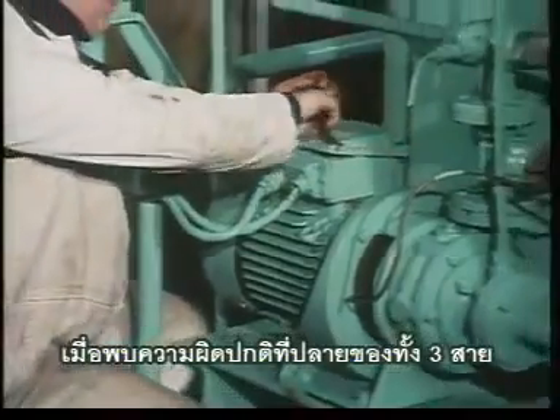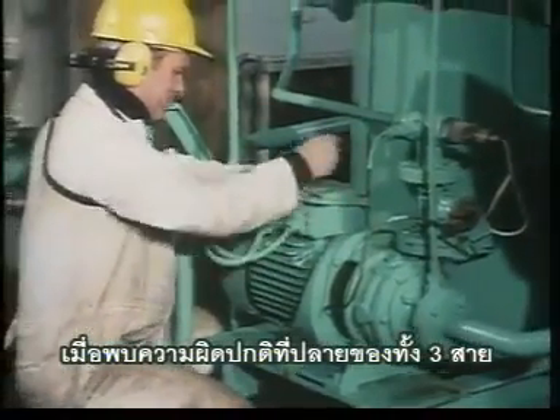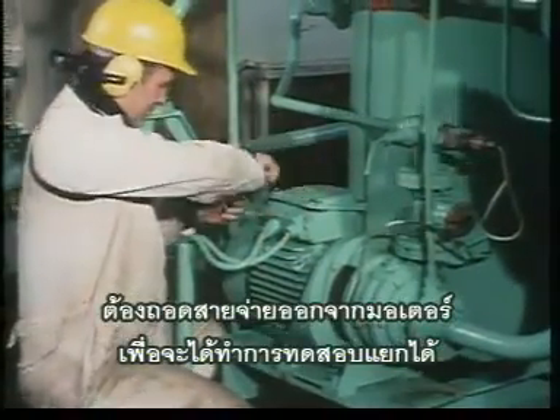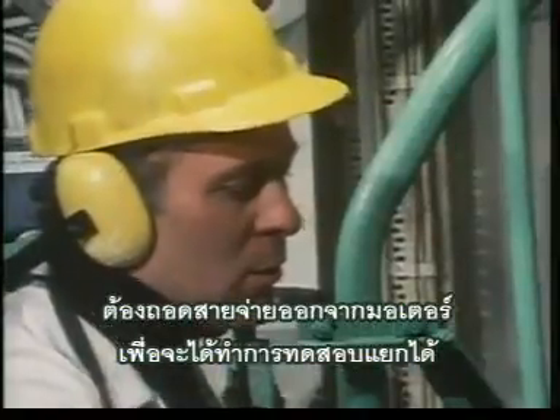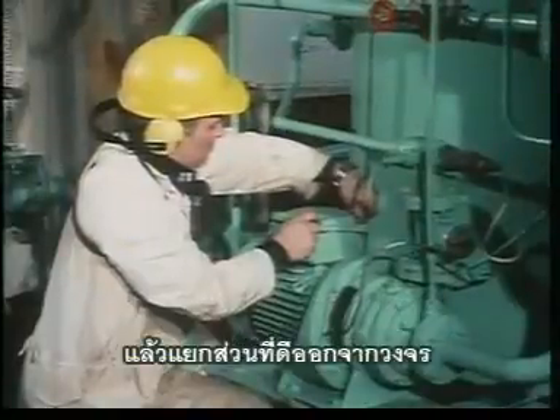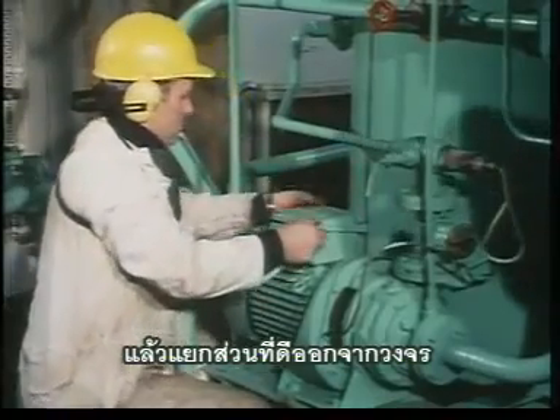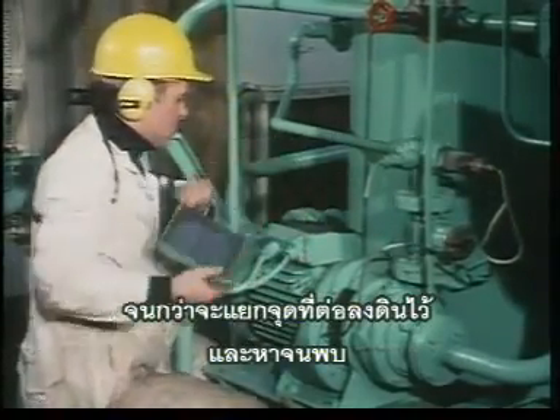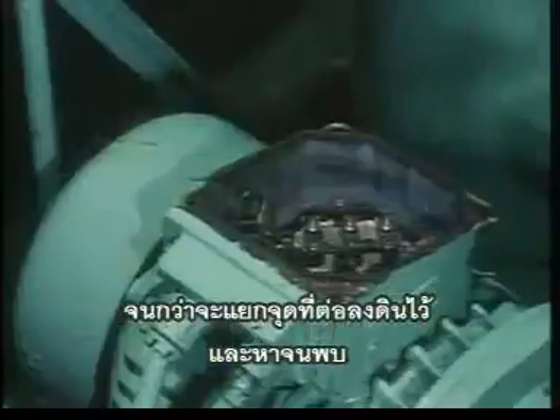Having found the earth fault on all 3 cable ends, the feeder cables must now be disconnected from the motor so that they can be tested separately, gradually eliminating the healthy parts of the circuit until the location of the earth fault is isolated and the fault found.